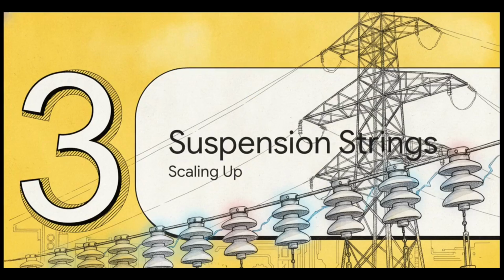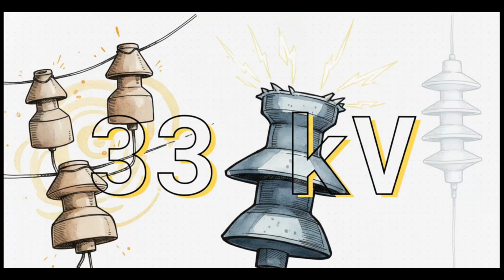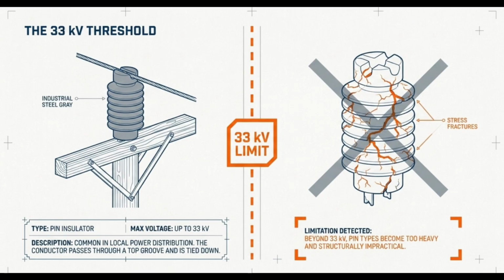Section 3: The heavyweight suspension strings and how we scale up. As our power needs grow, engineering has to adapt to handle much larger electrical loads, and 33 kilovolts represents a major threshold in power transmission. Historically, engineers used simple pin-type insulators for power lines, but once a line exceeds that 33 kV mark, those standard pin insulators become dangerously bulky and completely uneconomical to produce and maintain. The physics of higher voltages demand a totally different approach to keep the electricity isolated safely.